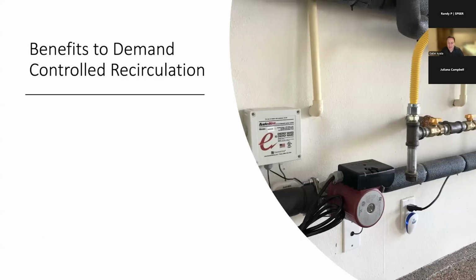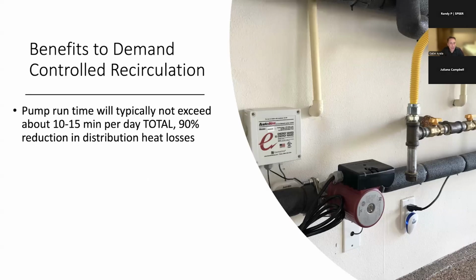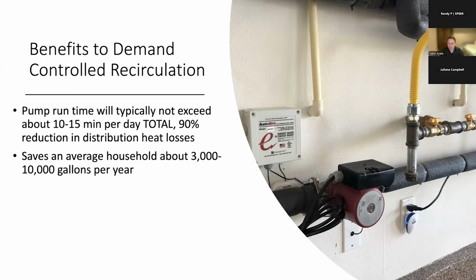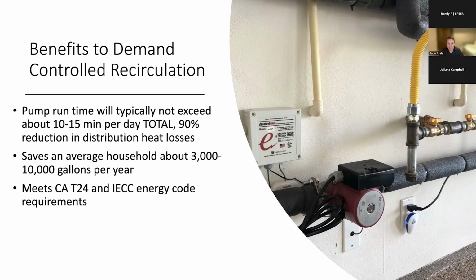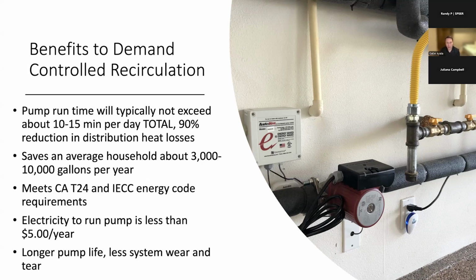Okay, so what are the benefits? Let me just recap the benefits of a demand-controlled pump. It's the reduction in total pump runtime. You get a 90+% reduction in distribution heat losses. You're going to get all the benefits of a conventional recirculation system: fast hot water, thousands of gallons of water saved per year. It's going to meet your local energy code requirements, and I'll talk a little bit about IECC. The energy to operate the system is only about $5 or less. And as I said, you're going to get a much longer useful pump life and less system wear and tear.